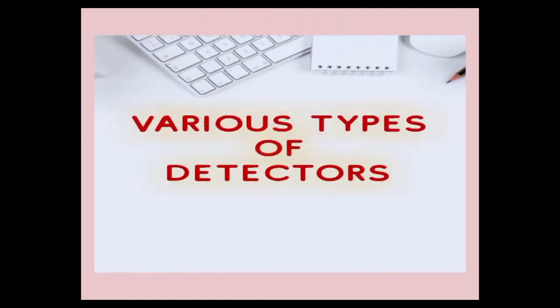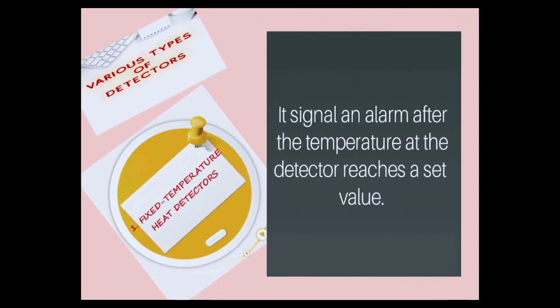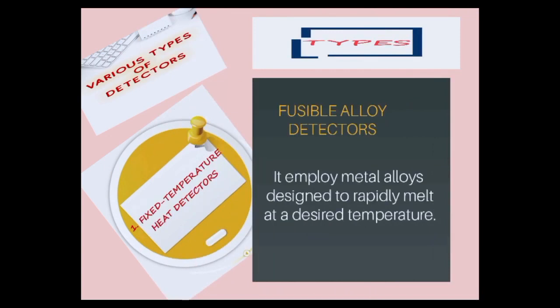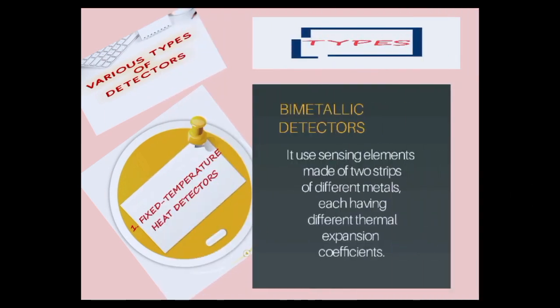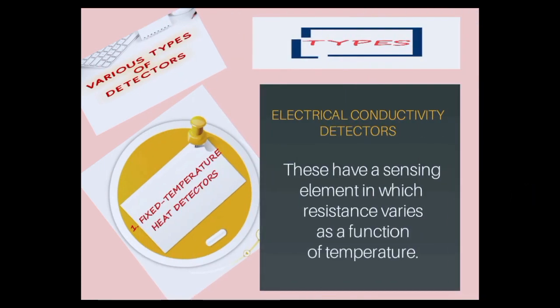Various types of detectors. First, we have fixed temperature heat detectors. It signals an alarm after the temperature at the detector reaches a set value. Types of fixed temperature heat detectors are fusible alloy detectors. It employs metal alloys designed to rapidly melt at the desired temperature. We also have the bimetallic detectors. It uses sensing elements made of two strips of different metals, each having different thermal expansion coefficients. We also have the electrical conductivity detectors. These have a sensing element in which resistance varies as a function of temperature.